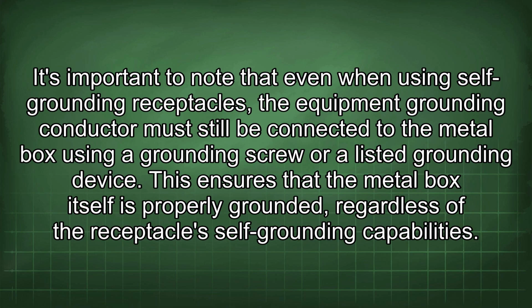It is important to note that even when using self-grounding receptacles, the equipment grounding conductor must still be connected to the metal box using a grounding screw or a listed grounding device. This ensures that the metal box itself is properly grounded, regardless of the receptacle's self-grounding capabilities.